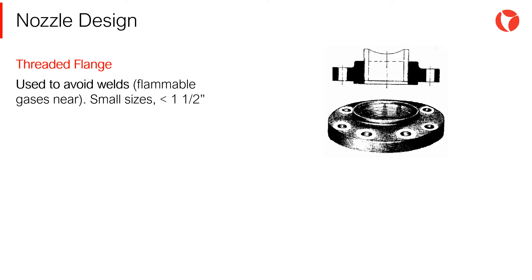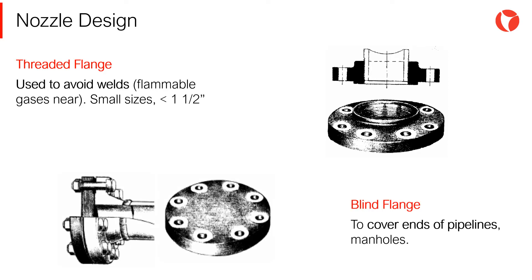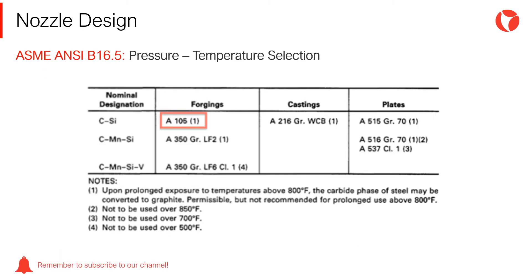Threaded flanges are useful when welding is to be avoided, for example in processes where flammable gases may exist. Finally, we have the blind flange, which is used to cover ends of pipelines, manholes of pressure vessels, and hand holes. These flanges have standardized dimensions and have been designed to withstand specific design conditions — pressure and temperature range. That is why they are not calculated, but selected.